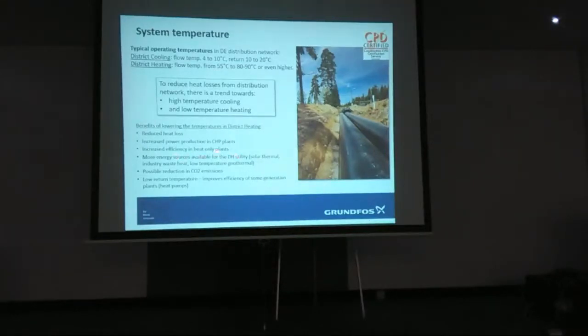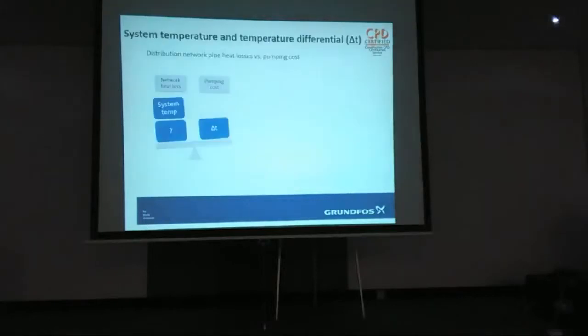Better efficiency if it's a heat-only plant. If you're talking lower temperatures, you can add more renewables, like solar, ground source, heat pumps and things like that. Reduction of CO2 emissions. I don't know how you really prove that, to be honest. But there you go. Lower return temperatures improve efficiency in some generation plants and in heat pumps. Yeah, okay. So the wider the gap, the better the overall efficiency.